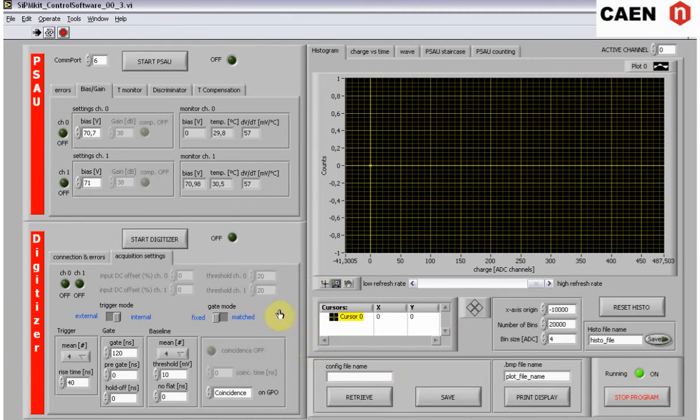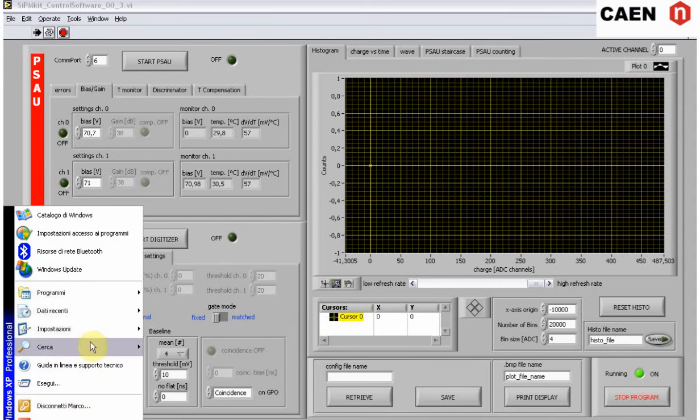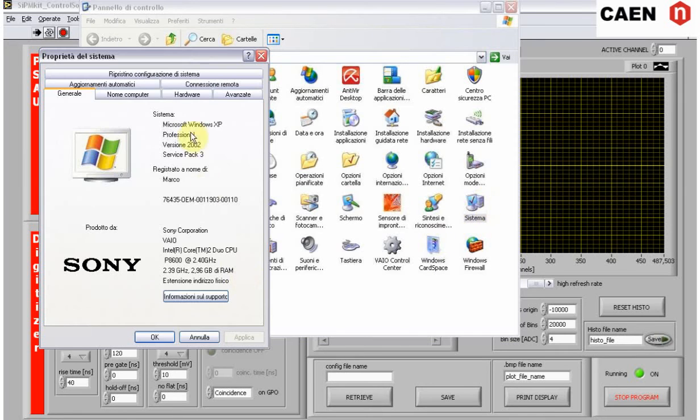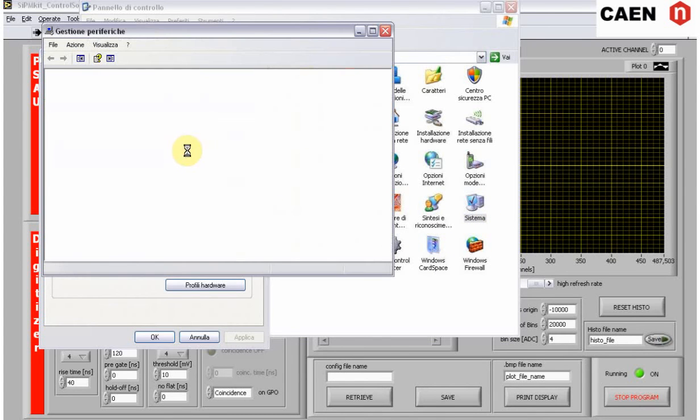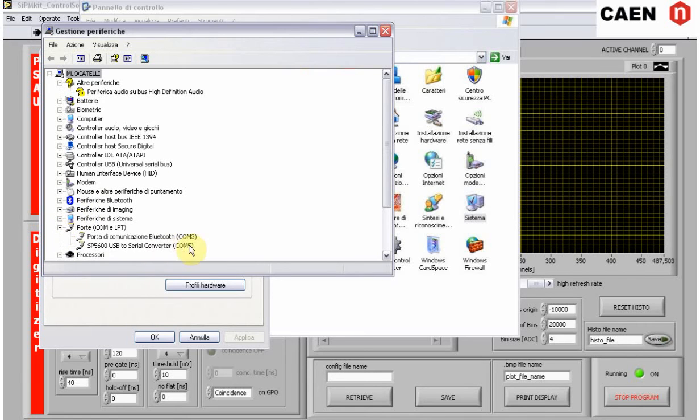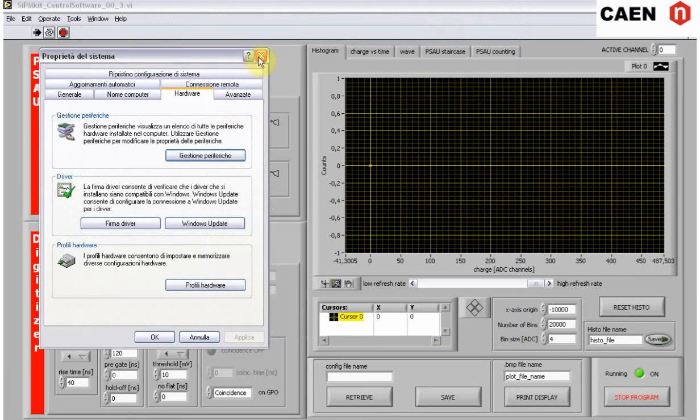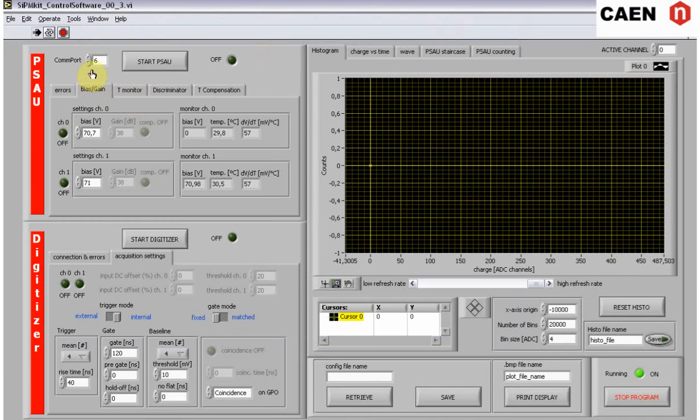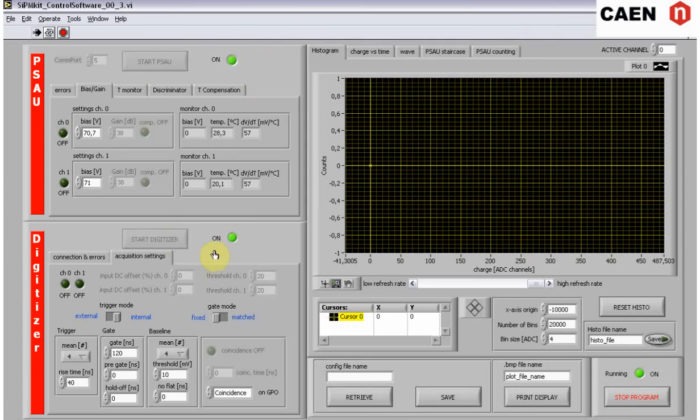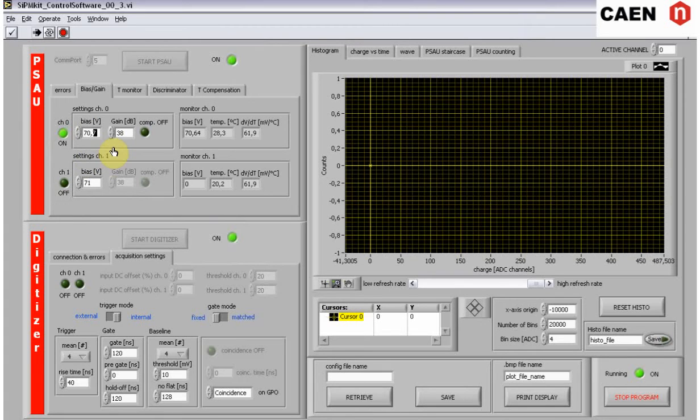Check the communication port of the PSAU. Start the PSAU. Switch on the channel you want to measure. Set the SIPM nominal operation voltage and set the gain of the PSAU amplifier.